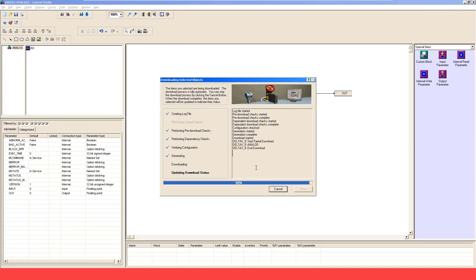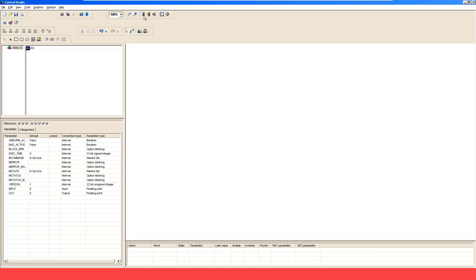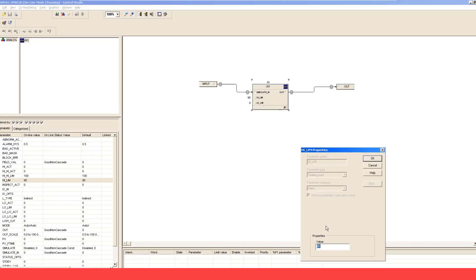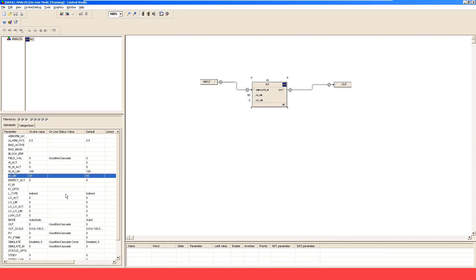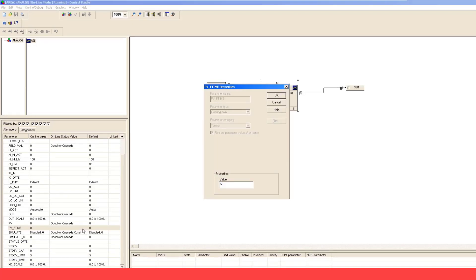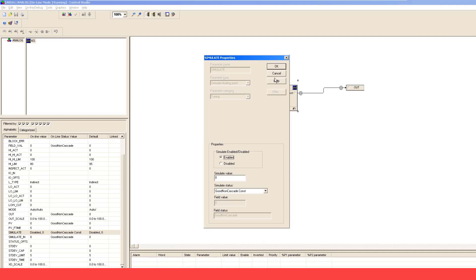Once you're done, save and download all so that all the changes you have made are downloaded. Then you can go online. These are the values we have — like 95 — you can change them. For instance, I can make the High Limit 80. You will see that 80 appears here. You can also change the PVF time — for instance, take it to 5 — and enable simulation.